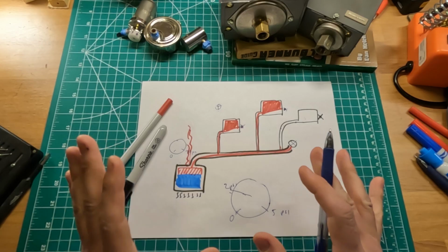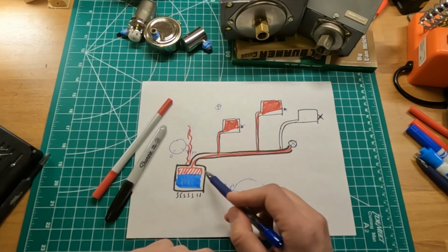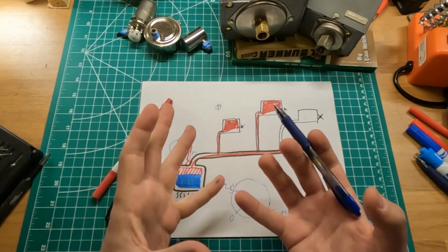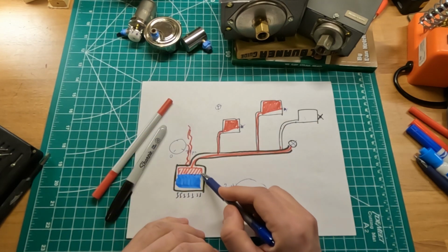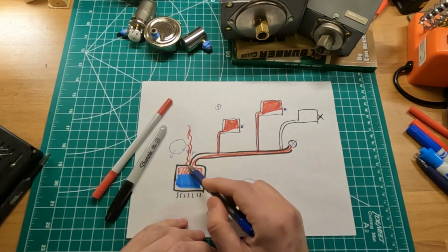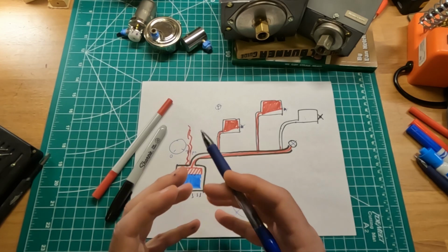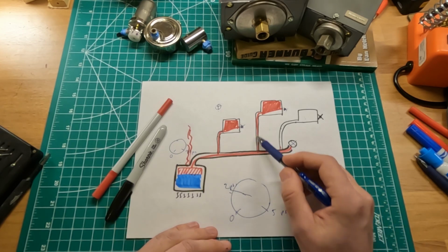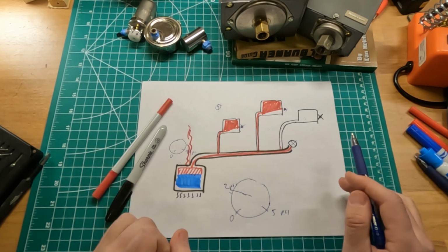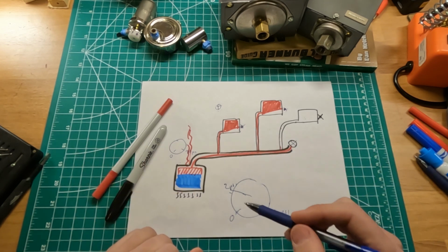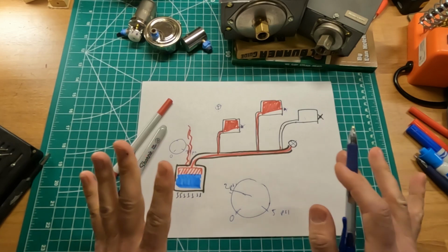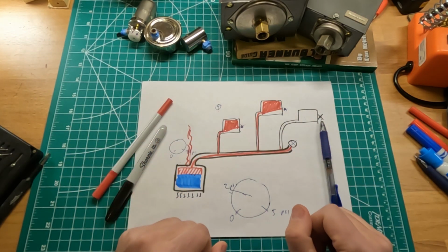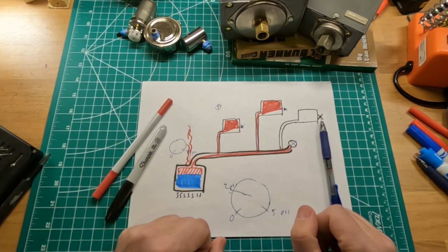and that's plenty of pressure for your system to go anywhere. Because you've gotta understand that it's not the pressure that really allows the steam to travel. It's the steam, by definition of being produced, because it expands 1700 times from the liquid state to the gaseous state. That expansion itself allows it to travel at quite incredible speeds to all those orifices to push the air out. So it's not the pressure itself. So keep the pressure as low as possible. And how to set the pressure controls and its failure points, that's the theme for another video. All right, that's that.